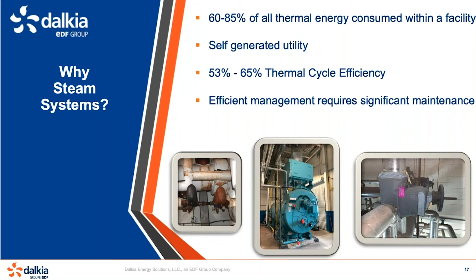Another item with steam is that efficient management requires significant maintenance, so it's not a set it and forget it type system. And so for the measures around the no cost, you see steam traps are a really big component there, and we see and hear from our customers that they've got spare traps on the shelf, they have bad traps, and so doing a study and properly managing those traps is big savings. We had one customer with one steam trap cost them $3,500 a year in lost opportunity or energy.